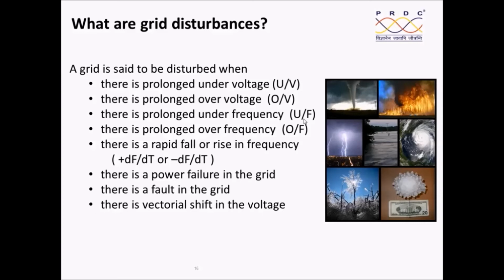We should not separate out at 47.5 Hertz, because after separating from the grid, we should have enough time for me to do the load shedding, and then the generator should trip. Therefore, there should be enough frequency margin and also time period available for us to do the load shedding. Therefore, we should not try to have the under frequency setting for the grid islanding at 47.5 Hertz. There is also a rapid fall or rise in the frequency, that is df by dt, or rate of change of frequency, a rise in the frequency or fall in the frequency.